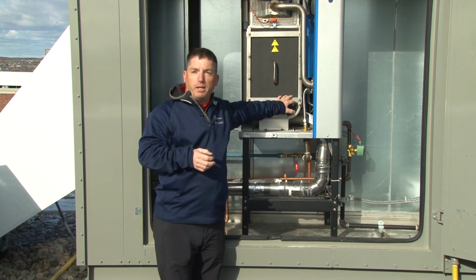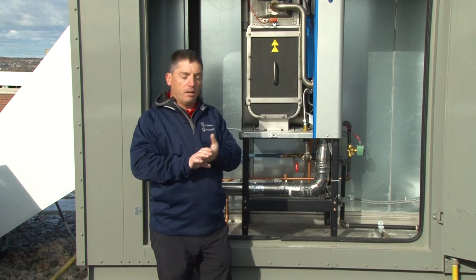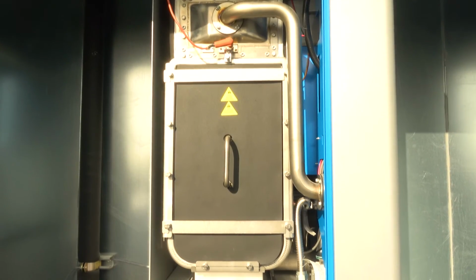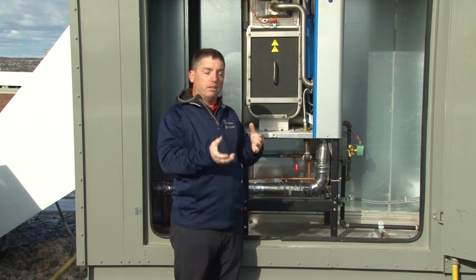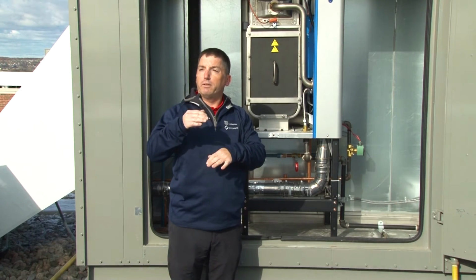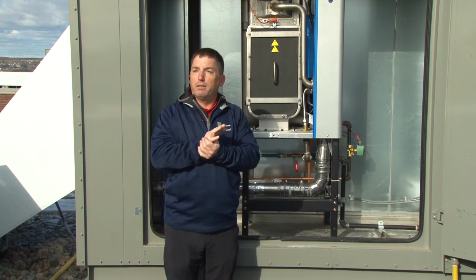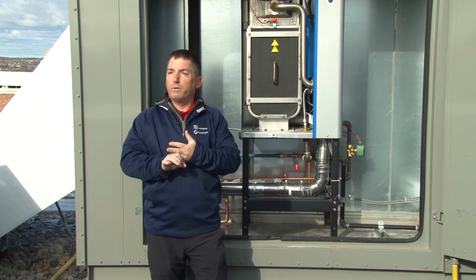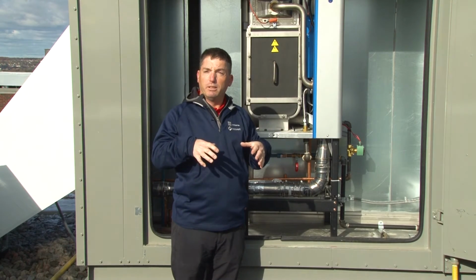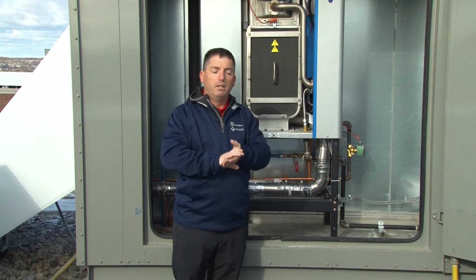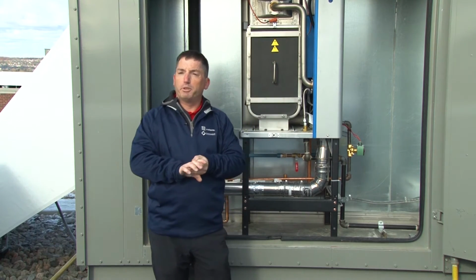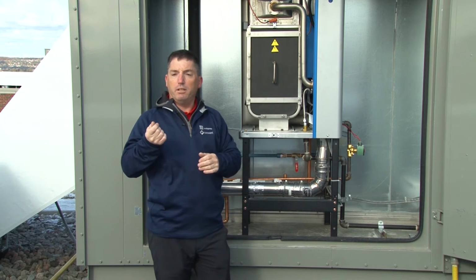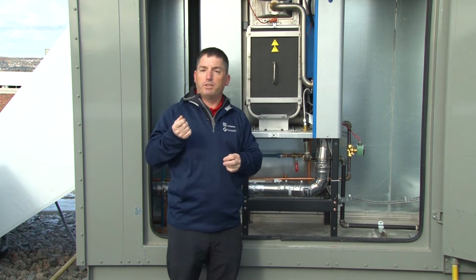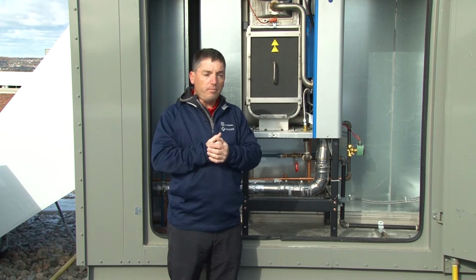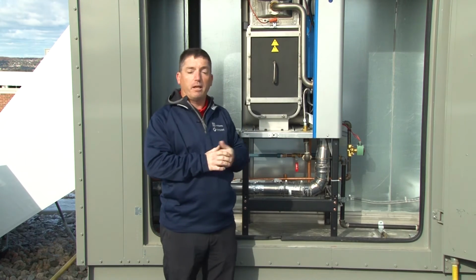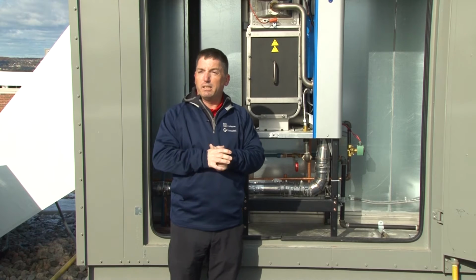Any surface scale that's left behind, if it's really thick, you can use a commercial cleaner called Rid Lime. You can fill the tank, I'd say 2/3 with water, put half a gallon of Rid Lime in, or you can use CLR or even vinegar. Just let that solution sit there and pre-treat the scale. You don't want to use any metal scrapers or brushes when you're trying to remove the scale, because even though it's stainless steel, the surfaces are relatively thin, and you don't want to damage either the tank or the heat exchanger. So plastic implements only.